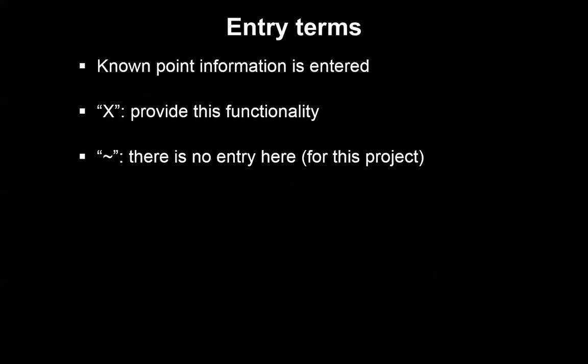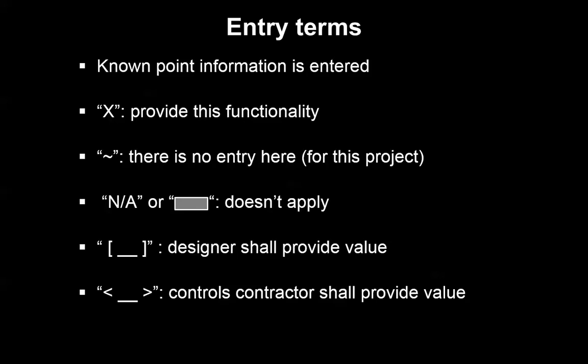So some of these entry terms. Well, the first thing you do is where you know information, where you know what points you want and what some of those set points may be, that would be directly put into the point schedule before it even gets to a designer. Where you see an X on this table, that's indicating that that is functionality that is required. Where you see this tilde symbol, that's indicating that there is no entry here. There could be, but for this project, there is no entry required. Where you see an NA or possibly some shaded box, that's indicating that an entry does not apply to that particular location. But really most important is going to be these brackets. So there's two types of brackets that we see on the point schedule. There's these square brackets, and then the angle brackets. And those are going to indicate who's responsible for putting and recording what information on different parts of this point schedule.